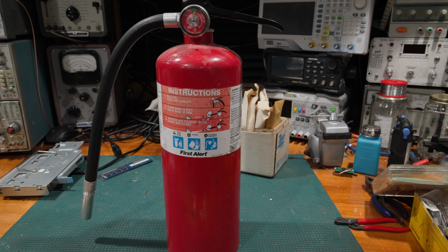The other thing too is, especially with fire safety in some of these systems, and arc flash specifically, an ounce of prevention is worth 10,000 pounds of cure. All of these fire suppression systems function, they work very, very well, but they make a huge mess, until you get into the gaseous ones, halon and CO2. The powder fire extinguishers make a huge mess, and water gets everywhere, gets into everything.